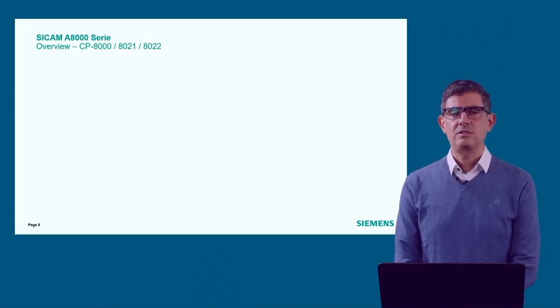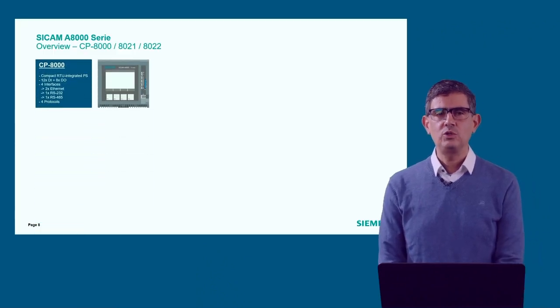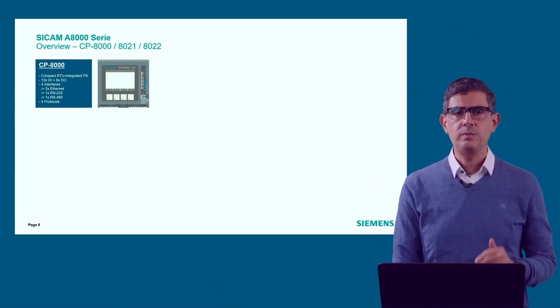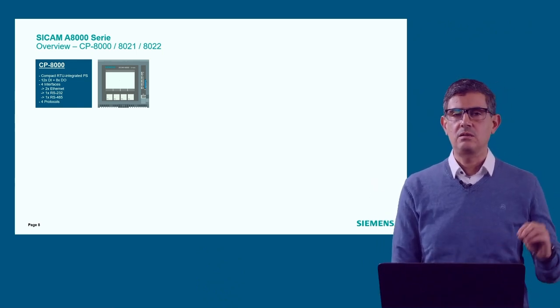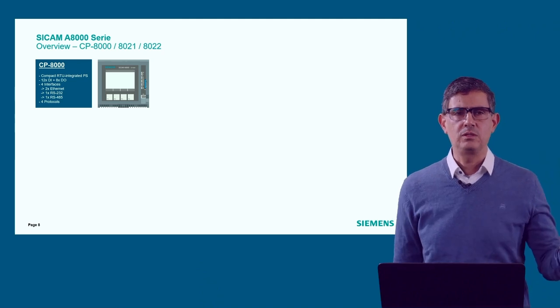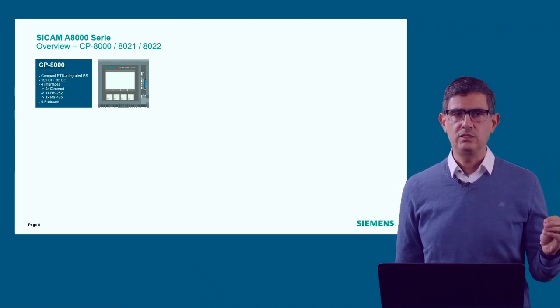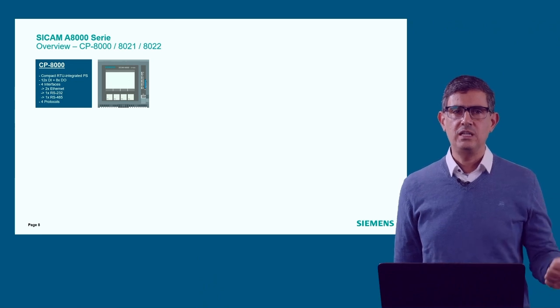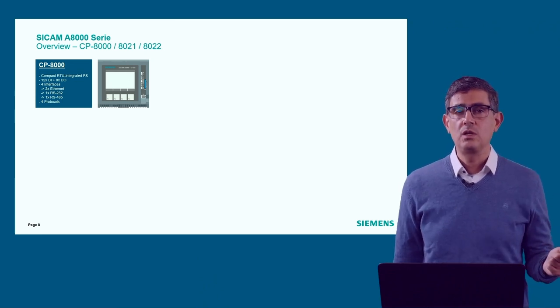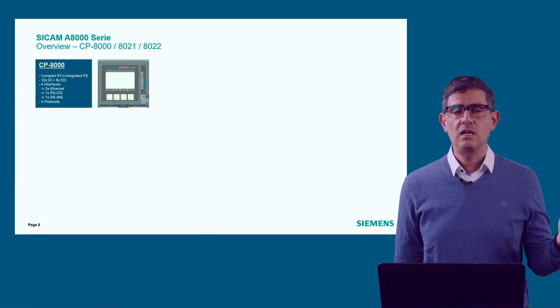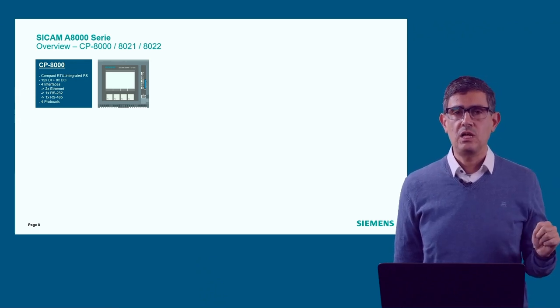All the SICAM 8000 family started with this small RTU you can see on the screen, the CP8000. This is a compact RTU which is fully equipped already. It has one 24-volt power supply included, one module with binary inputs, one module with binary output, four interfaces — two of them LAN ports (Ethernet) and two serial ports. It supports four communication protocols and up to 20,000 data points.